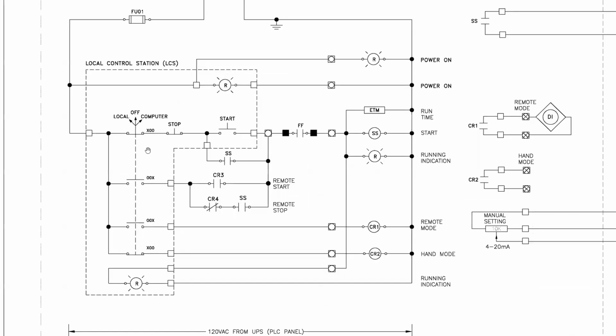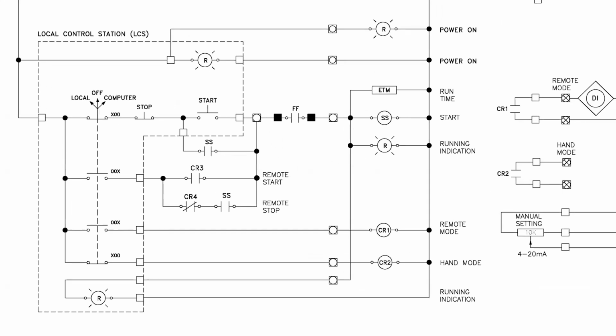One of the things, this is a good one. This is probably the main reason I picked these drawings. You can see here, you've got a local off computer. This is a 3-position selector switch. If there was an indication, if this were broken, if you had a selector switch that did something like this, it could indicate that maybe, let me undo that for a second, because there would never be one like that. So if there were some sort of spring, a switch that looks something like this would indicate that it could be 2-position with a 3rd position. Because that's broken, it may spring back to the center.